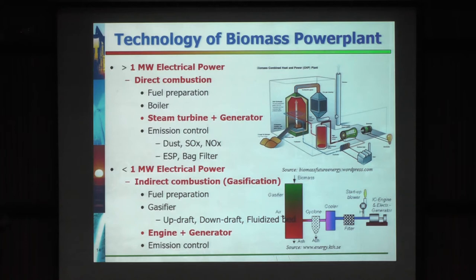But for the small scale power plant, for example, a plant that produces less than 1 megawatt, we use indirect combustion or gasification. Of course, by using this technology, we need to prepare the fuel to be dry and feed the dry biomass into the gasifier. There are different kinds of gasifier that we use, either updraft gasifier, downdraft gasifier or fluidized bed gasifier. And as you know, we can get CO gas, methane and hydrogen, with the tar, which is really dirty.